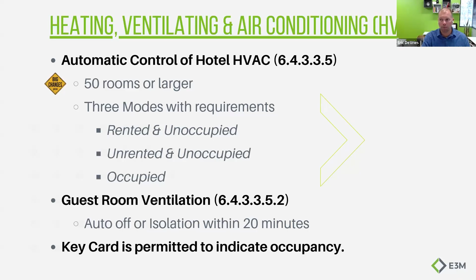A couple other kind of smaller changes here on the HVAC side. I love this one. I'm a big fan of this. If you have the ability for your system to humidify and dehumidify, you have to have an interlock that literally allows one or the other. An exemption to this is a hospital surgical type setting. You have the ability to humidify or dehumidify within really tight bands. That's a life safety issue and an exemption, but in general, an office building might have a humidifier and like a hot gas bypass or another way to dehumidify. They want to make sure that those are interlocked so they can't run simultaneously.